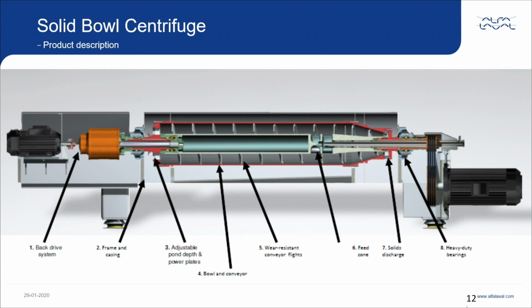So this is the conveyor shaft, and it is hollow until the end of the feed tube, and thereafter it's a rigid shaft. And on the conveyor you have helical flights. So as soon as the feed enters the bowl, the suspended solids get thrown against the internal wall of the bowl by virtue of high centrifugal force, and then it's the duty of the conveyor to convey those solids and bring them out from the solid discharge port, which is located on the conical side of the bowl. And the clear liquid, after separation, travels in the opposite direction and comes out from the liquid discharge ports.